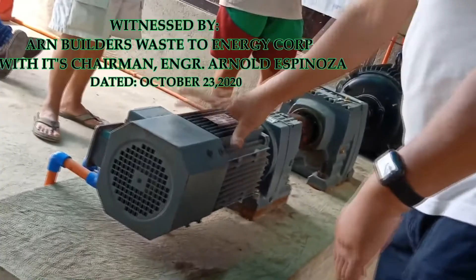So this is the sequence. The other variable frequency drive will stabilize and take over. The generator will power back to this motor and then it will recycle the power. And the fan motor, you start the fan motor first because this is a different motor. This is the first power from the generator, which is 380 volts, for the fan motor. It's okay now. Okay, you change over.